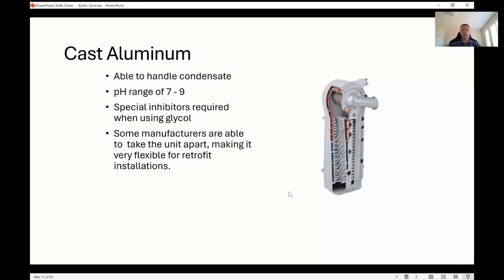Cast aluminum is another product out there. It works well in a condensing situation. It's able to handle condensate. Usually with this type of appliance, what they've done here is they've kind of mimicked almost what a cast iron was. If you take a look here, there's all those heat transfer pins there. Flue products are at the top. The flue products are forced downwards. As it gets closer to the bottom, it's a counterflow type design. It's going to start raining in there, and it's going to start condensing, and that condensate will pool up at the bottom and be piped out of the unit.